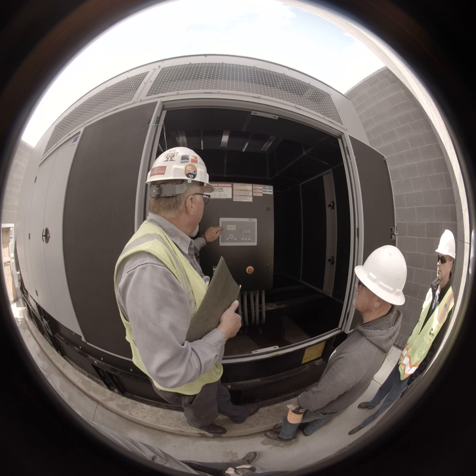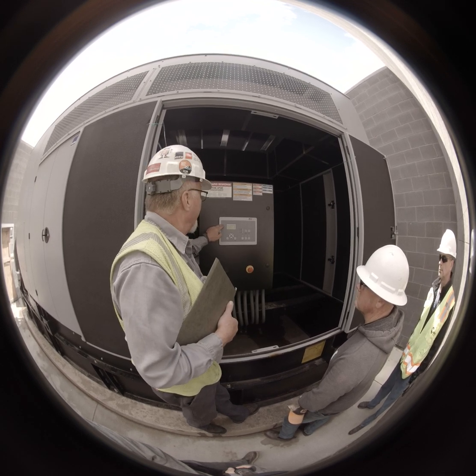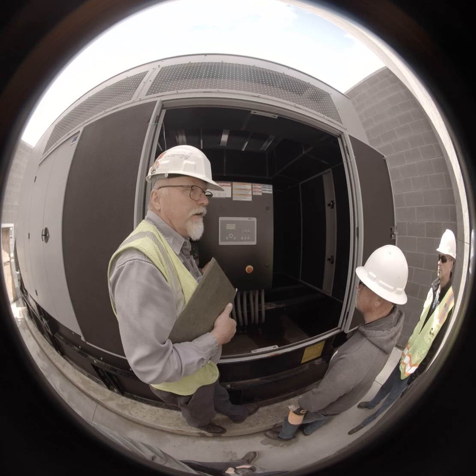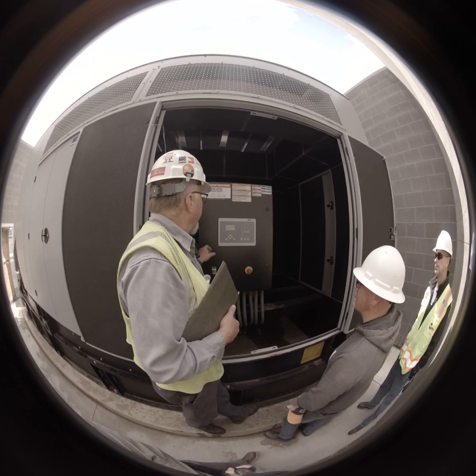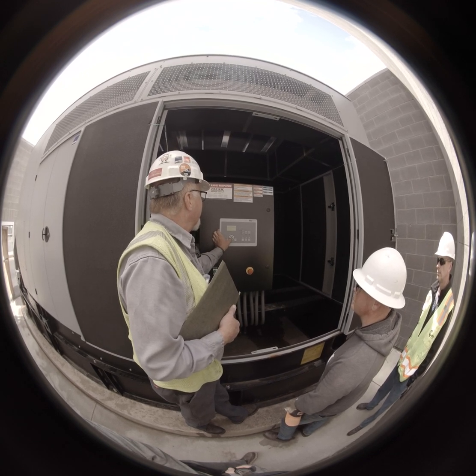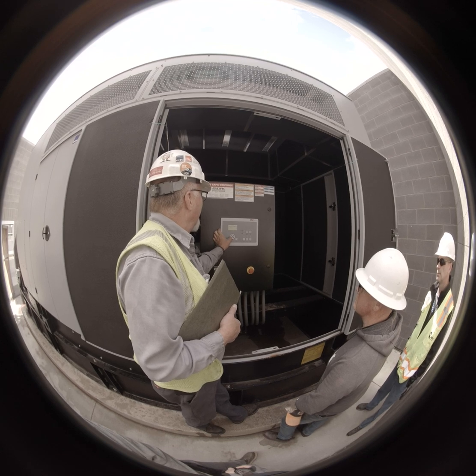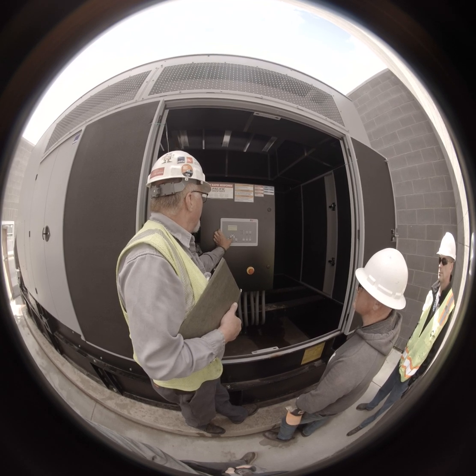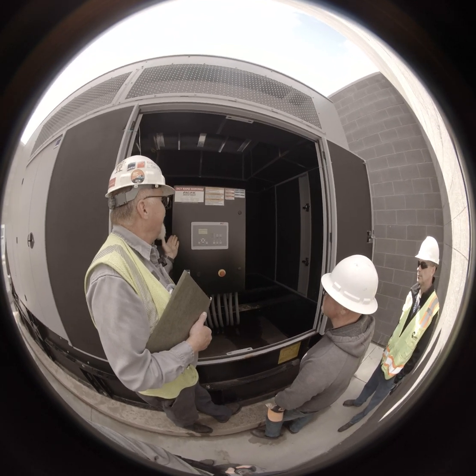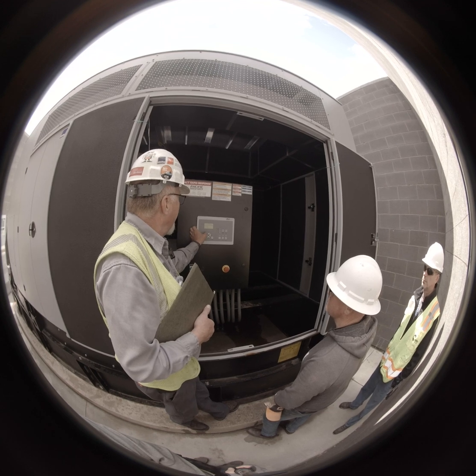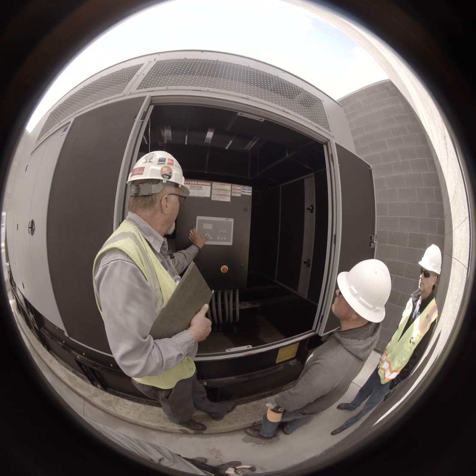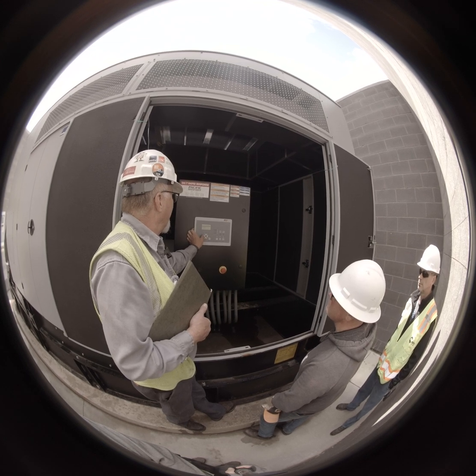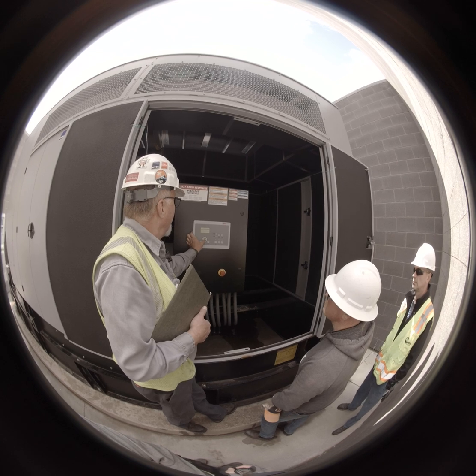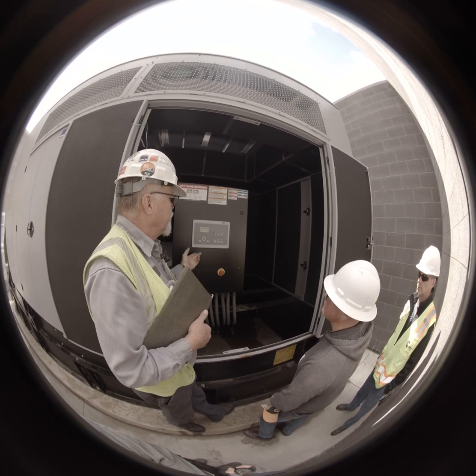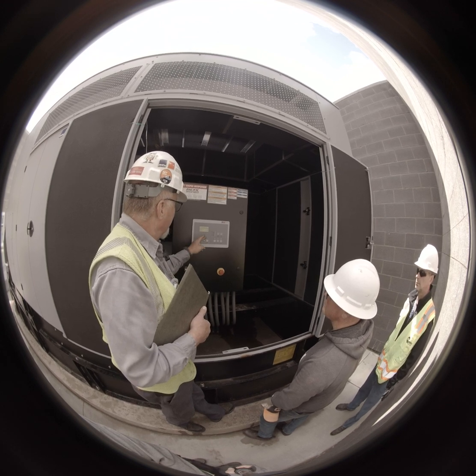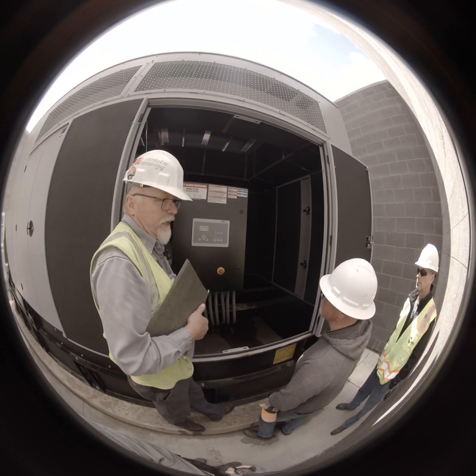So, and it has a lot of, EPS supplying load, as I was telling you about the 3% on that. And we do not have a mains breaker on this. The mains breaker is off board in the other cabinet. But you can actually look at the status of all these things. The same with inputs. I mean, it's endless what you can look at in here. Battery charger failed, fuel leak, coolant level. And then you can do the same with your outputs. You know, engine's trying to start, but it's not starting. Well, you can see that yes, it closed the relay, or no, it didn't close the relay.